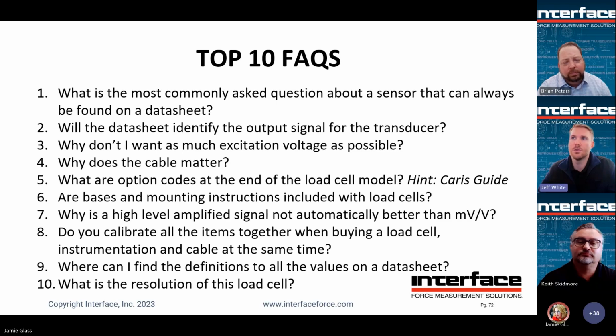All right, so what are the option codes at the end of the load cell model? Richard Karras decided to incorporate option codes into all of our load cells. Unfortunately, there's no real rhyme or reason, but you might see ACK or AF or AJ, and these define the feature codes within the load cell. So if you get a new load cell from us, you'll know it, but if you find one out in the field and want to know, please contact us, and more than likely we'll be very happy to let you know the option codes or the feature codes within the option code. And we've got the Karras guide up there to address some of the more common ones that are out there. So it's on the website.